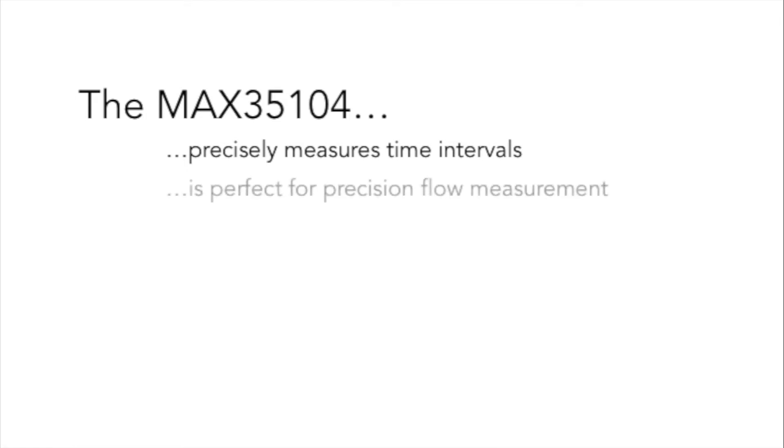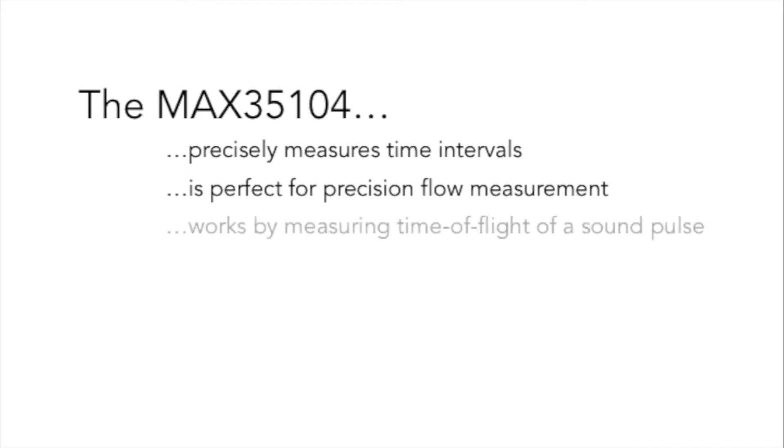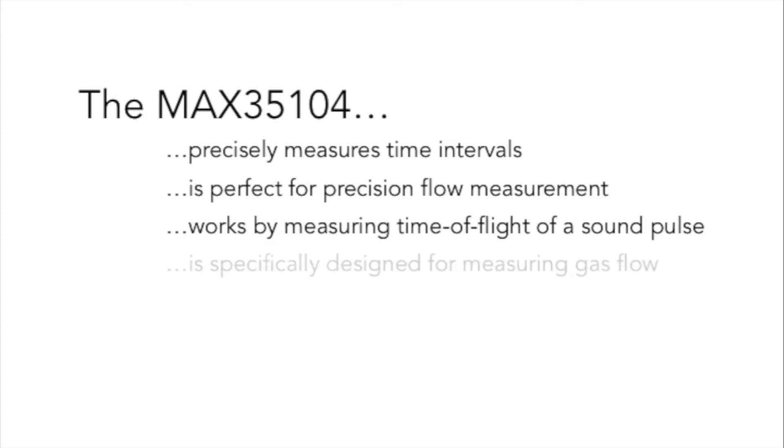They're most frequently used to measure fluid flow rates by computing the difference in the times of flight of ultrasonic pulses transmitted in the direction of the fluid flow and pulses transmitted against the direction of the flow. In particular, the MAX35104 contains additional circuitry that allows its use for gas flow measurement.